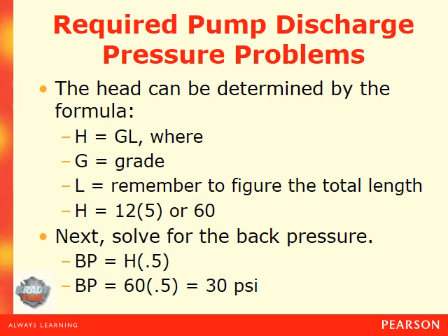Now we've got to figure out our head pressure. So we had our 12% grade, and we were going to do 0.5 per foot. So 60 times 0.5 in height, because again we're going up 12 feet per 100 feet. So I misspoke a little earlier, but that's 12 per each 100 feet. We have 500 feet, so that gives us 60. And then 60 times 0.5 per foot gives us an additional head pressure of 30 psi we've got to figure out.